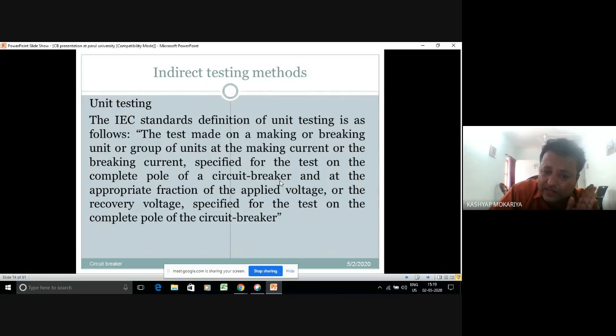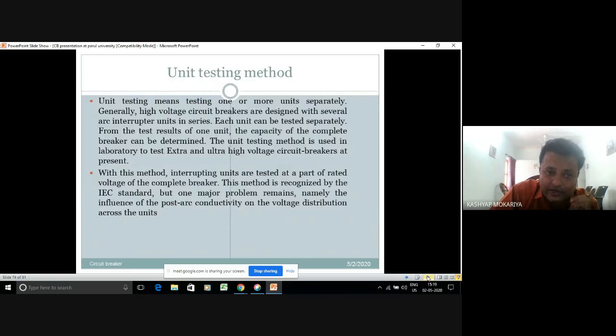Now we are not talking of three pole. Now we can talk about a complete single pole unit also in unit testing. That's why it was named unit testing. Unit testing means testing one or more units separately. Generally, high voltage circuit breakers are designed with several arc interrupter units in series. Each unit can be tested separately. From the test result of one unit, the capacity of the complete breaker can be determined.